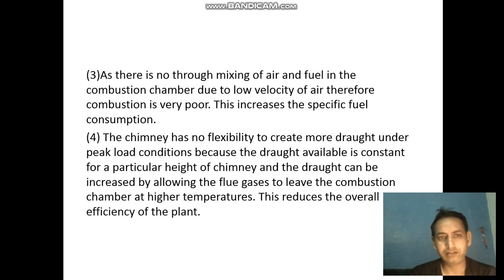And as there is no proper mixing of air and fuel in the combustion chamber due to the low velocity of the air, because the draught is lesser, the air passing through the grate has low velocity, so proper mixing is not there, and the specific fuel consumption increases. The fuel consumption increases for developing the same amount of power as in the case of the artificial draught system.